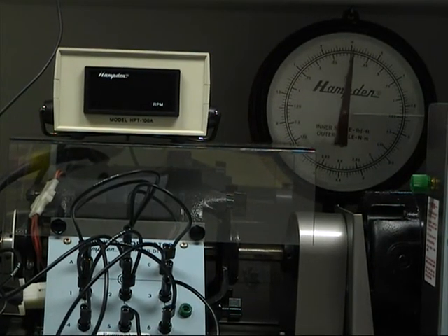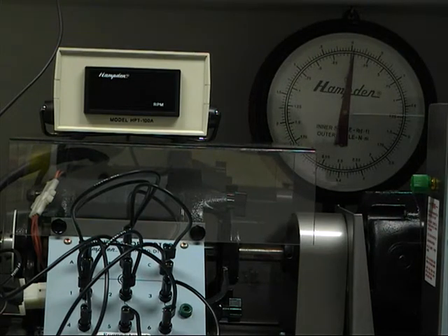I'm going to give a demonstration of an open loop drive system. For an open loop control of an induction machine, the speed of the induction machine is related to the frequency supplied by the power processing unit. So we are going to adjust the frequency coming out of the power processing unit and see how that controls the speed. So we'll start off by applying 30 Hertz to the machine and look at the speed that we get.